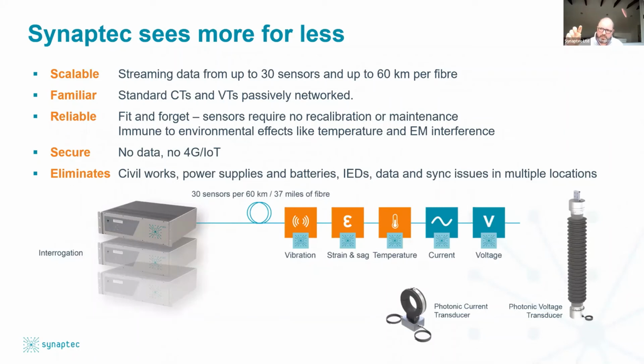Also, those devices could be primary connected, like the pictures you see here, or they could be secondary connected, which some customers ask us to do, to take advantage of the fact that they've probably got CTs and VTs at the substation end, and it's only the remote end that needs additional sensors for the purposes of faulted section identification, let's say, and creating new electrical sections that you want to discretely monitor.